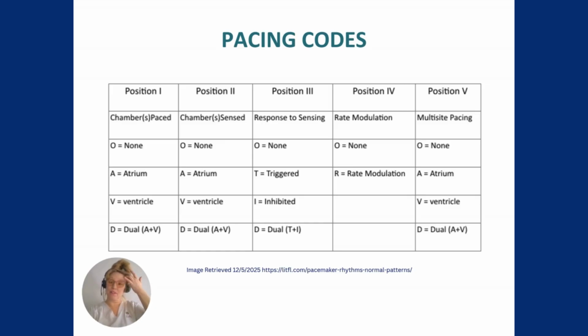This slide helps us decode pacemaker modes, so we don't have to memorize them, we just have to think through them logically. So remember, the first letter tells us what chamber is paced. The second tells you what chamber is sensed. The third letter tells you how the device is responding, so either triggered, inhibited, or dual.